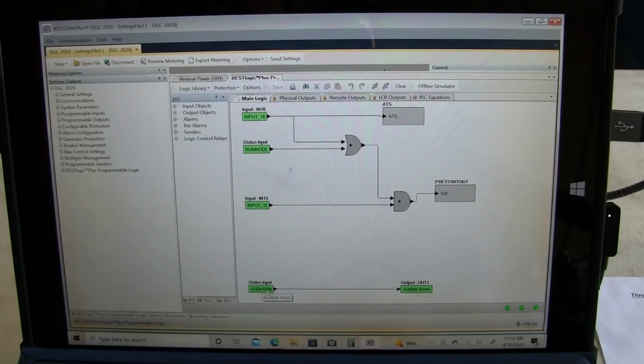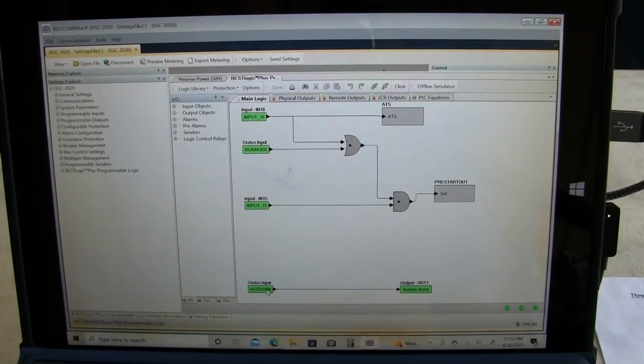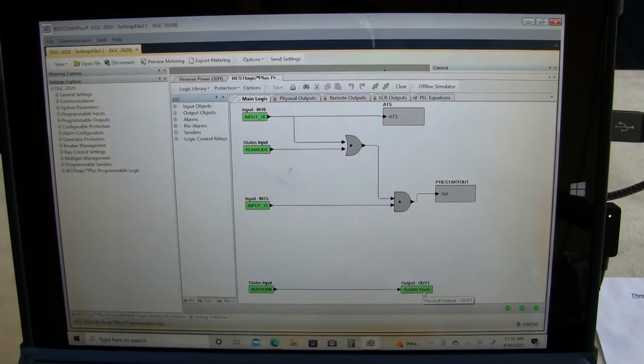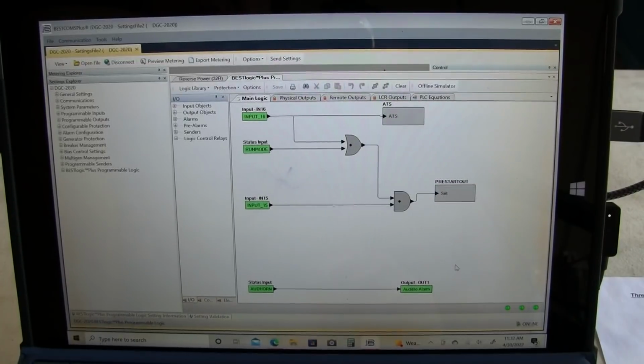So when the audible horn, AUD horn, whenever the controller wants to trip or activate the warning siren, the audible alarm, it picks up output 1, which I have labeled as audible alarm, and that powers the little buzzer up at the front of the panel. So really the only piece of logic here is the preheat enable or disable, which is that second toggle switch on the front panel. So let's go to the simulator.